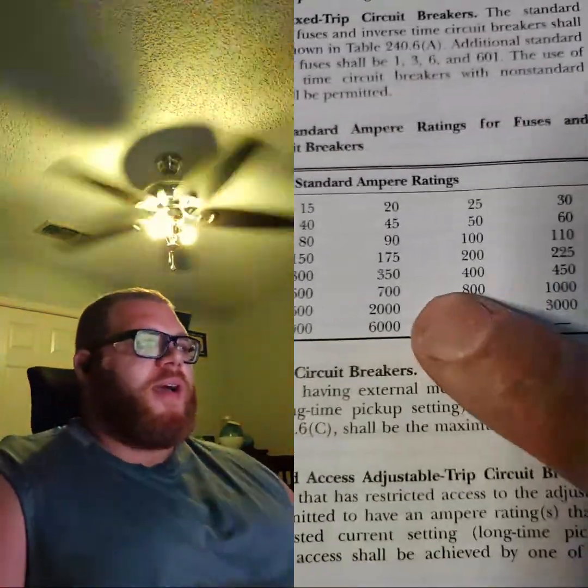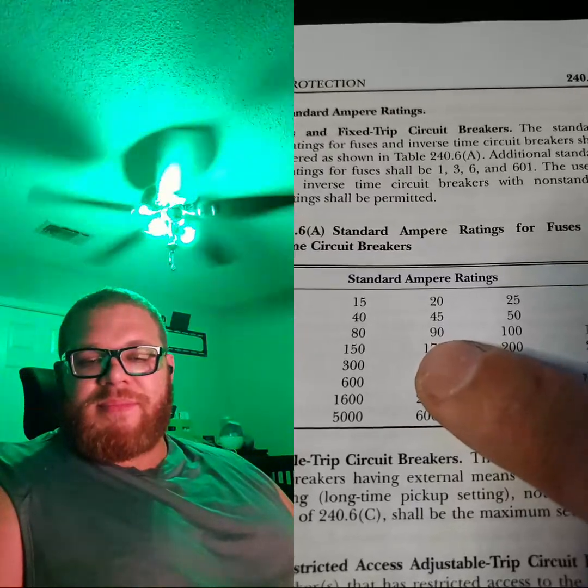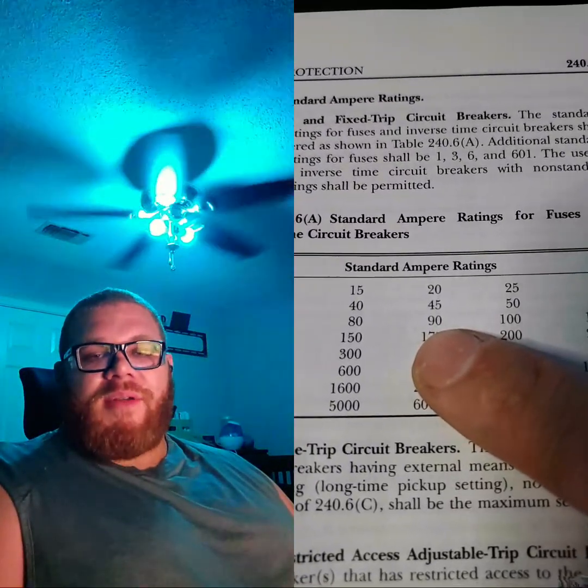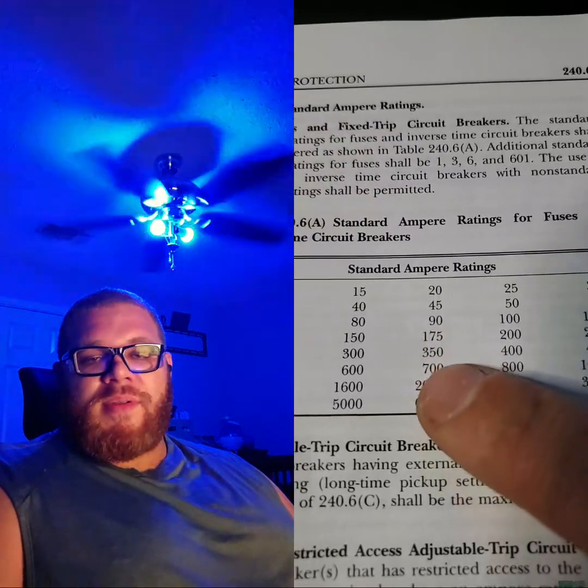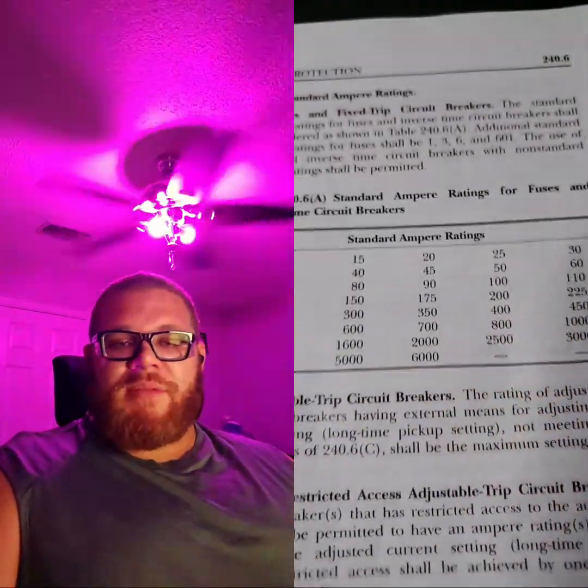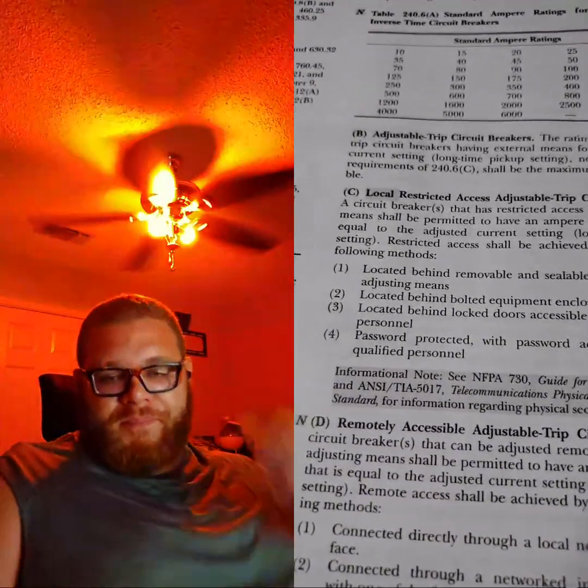No, I understand about rounding up from 375 to 400. I just don't understand how that's going to feed 25 mobile homes. Seems a little light. Did you know that 90 is a standard amp fuse? Yeah, I know 90 is a standard amp fuse. So you know 350 could have been. Yeah, I know the 350 standard fuse size, but 375 is not. Yeah, I know you got to round up. That cannot be right. This thing's messed up. Nobody's doing a demand factor of 24%. Yeah, I see that. Yeah. Next. Next.